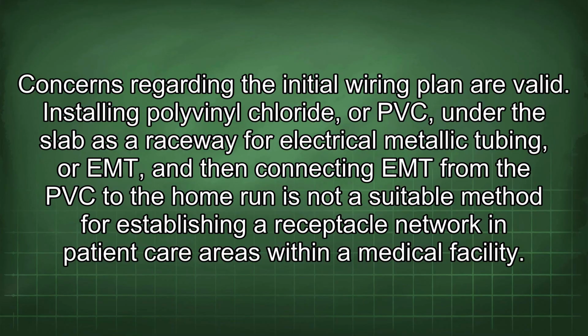Concerns regarding the initial wiring plan are valid. Installing polyvinyl chloride, or PVC, under the slab as a raceway for electrical metallic tubing, or EMT, and then connecting EMT from the PVC to the home run is not a suitable method for establishing a receptacle network in patient care areas within a medical facility.